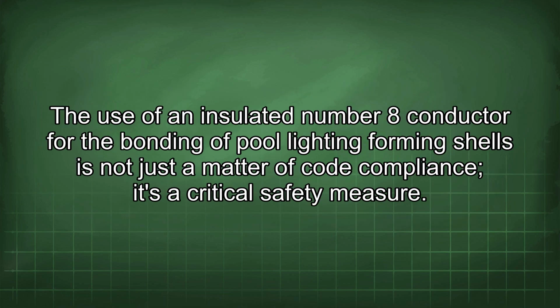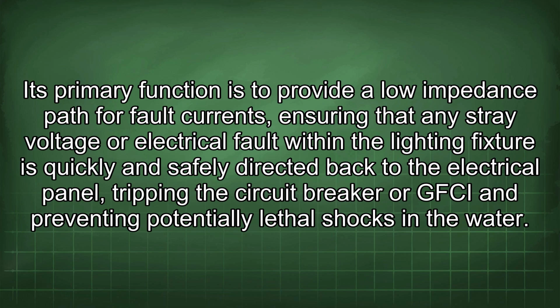The use of an insulated number 8 conductor for the bonding of pool lighting forming shells is not just a matter of code compliance, it's a critical safety measure. Its primary function is to provide a low impedance path for fault current, ensuring that any stray voltage or electrical fault within the lighting fixture is quickly and safely directed back to the electrical panel, tripping the circuit breaker or GFCI and preventing potentially lethal shocks in the water.